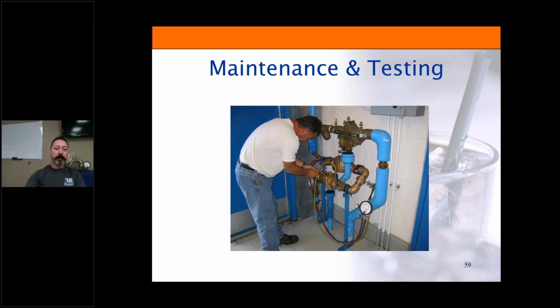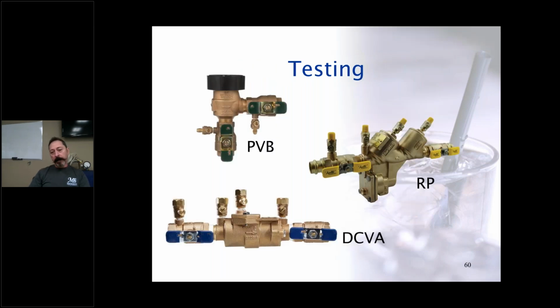Testing and maintenance of backflow preventers. Some backflow preventers require annual testing and maintenance and can be done by closing the shutoff valves, pulling it apart, repairing it, putting it all back together, and conducting a test to ensure that the check valves function properly. Now, of the different devices, there's a pressure vacuum breaker, an RP, or a double check valve assembly. These devices are all testable, and they get tested when they're installed, and then annually thereafter is sort of your best practice for time frequency.